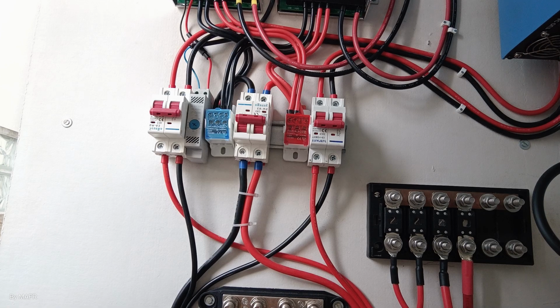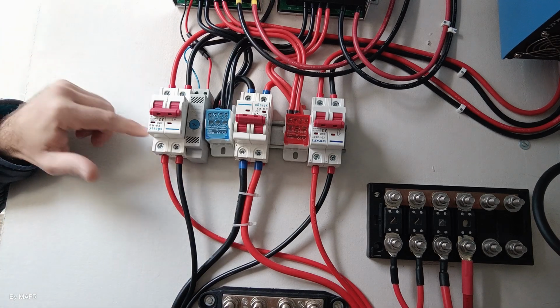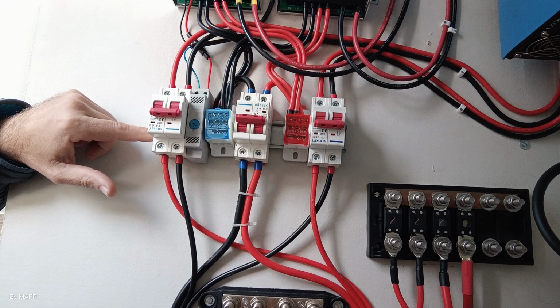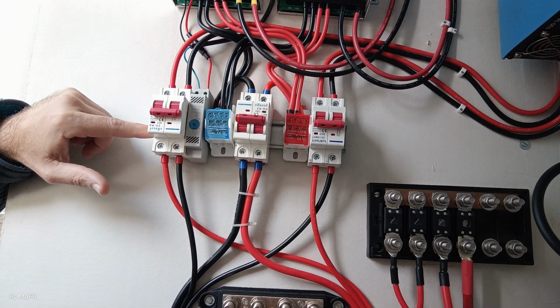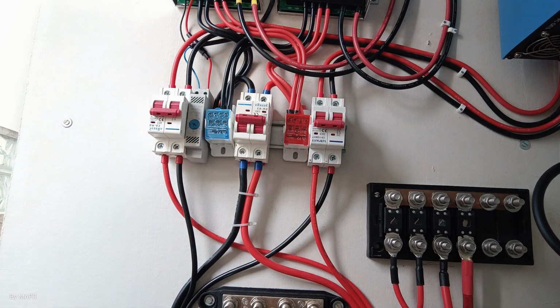Keep in mind that my solar panels here are not too many. I have on the roof 6 panels divided in 2 arrays, each array with 3 panels. Each panel has 425 watts, 36 volts roughly, and as they are in series, each charge controller gets 99 volts closed, 110 volts open, and 13 amperes. So very efficient system, working perfectly.